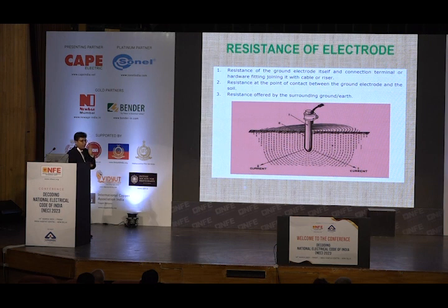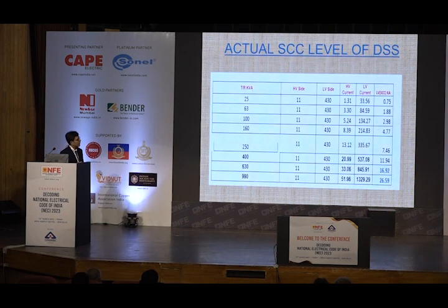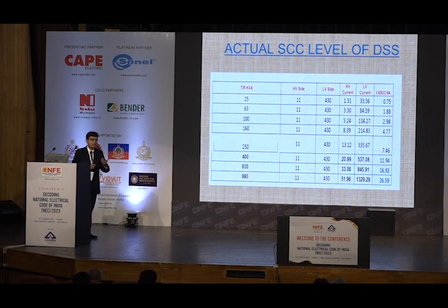Because the main contribution is of Mother Earth in the vicinity of your earthing system. With some methods you can improve, but you can't do magic. For all these things, the important part is the short circuit understanding of the systems you are working in. These are the normal transformer ratings we usually come across: 25 kVA, 63, 100, 160, 250, 400, 630, and corresponding to the DT you are using in your system, I have given some short circuit levels. Based on that short circuit level, you have to select your earthing conductor and your electrode.